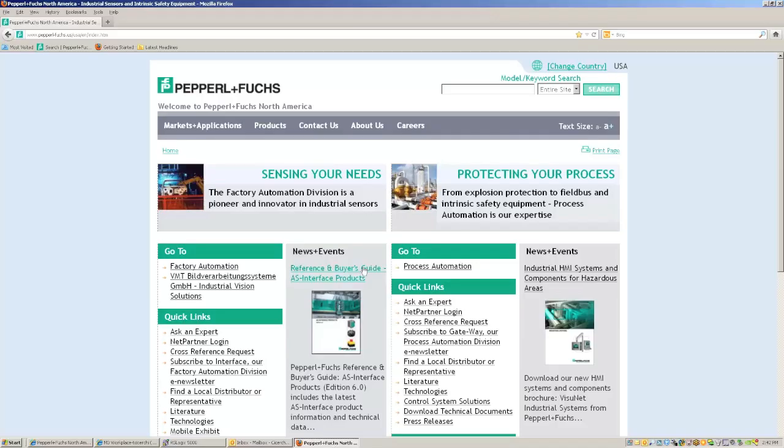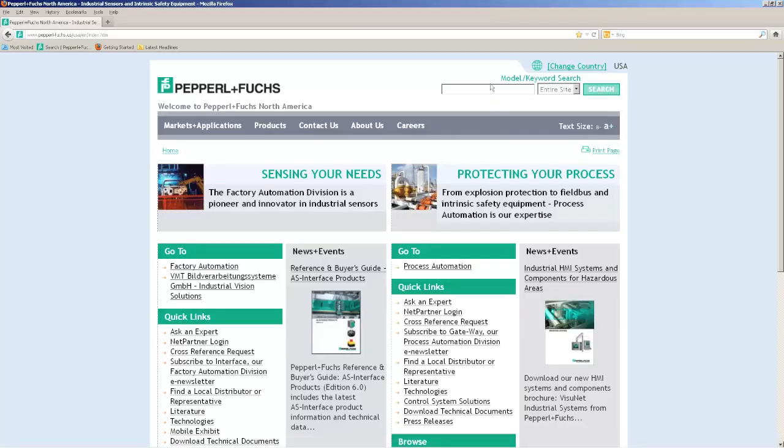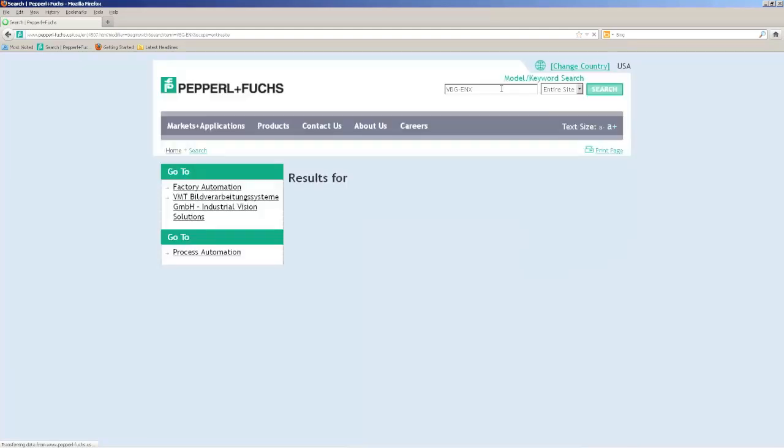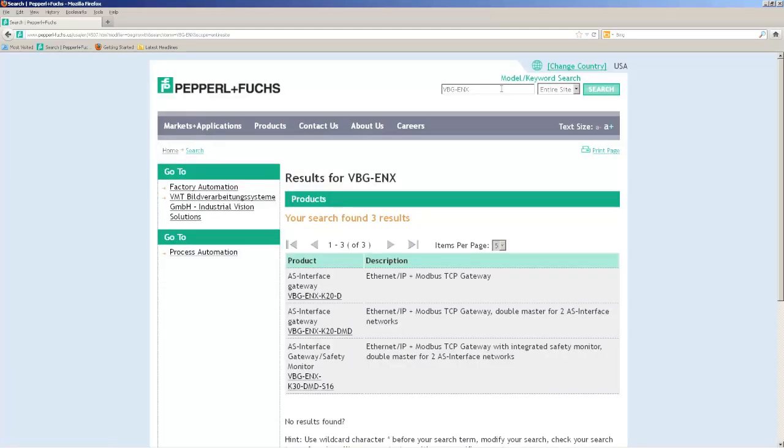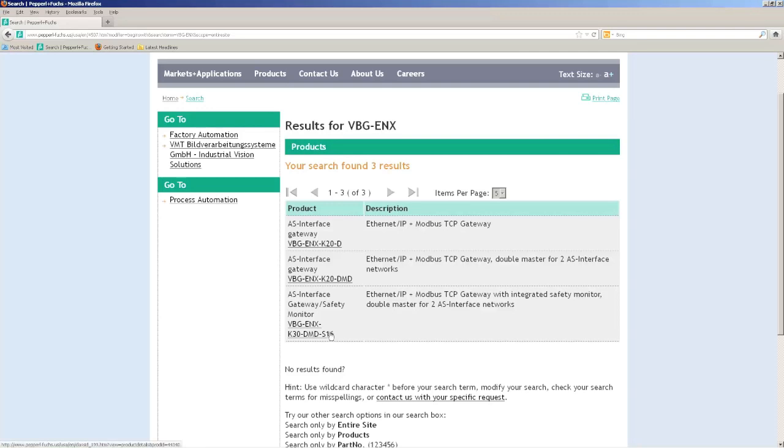So now I want to show you how to program the Ethernet IP ASI gateway with the Allen Bradley RSLogix 5000 software. The first thing I want to do is download the correct drivers. I'm going to go to our website pepperl-fuchs.us and just type VBG-ENX in. This will pull up the three different gateways that can be an option for you: the single network gateway for Ethernet IP, dual network, and dual network with safety monitor. That's the one I have, so I'm going to click on that.